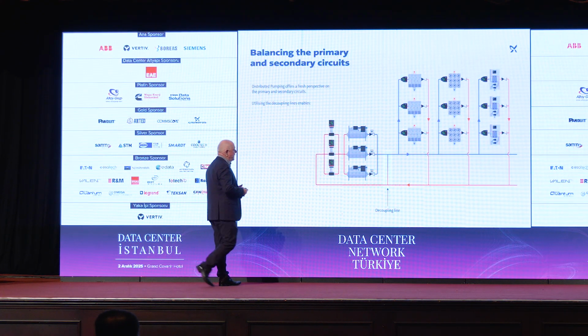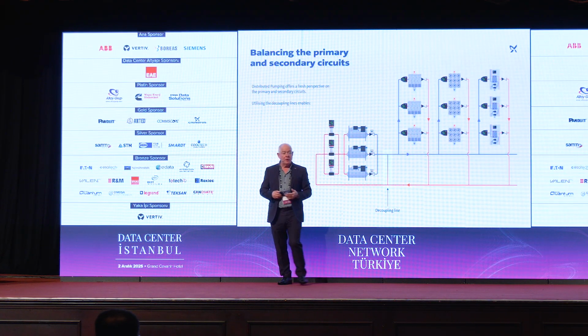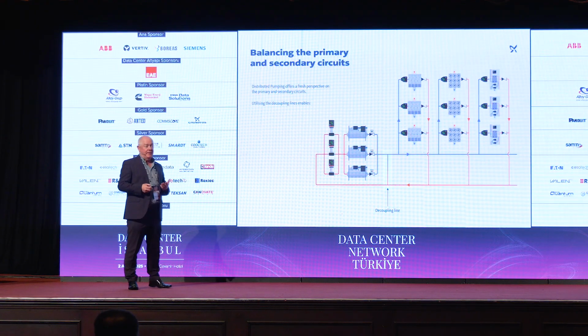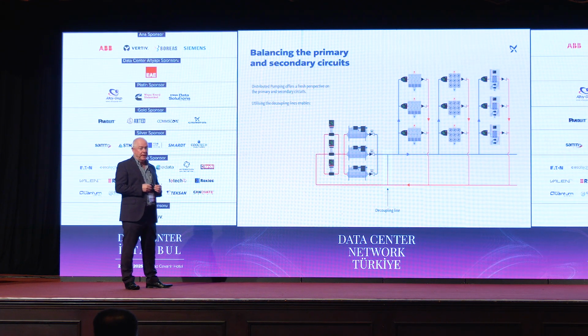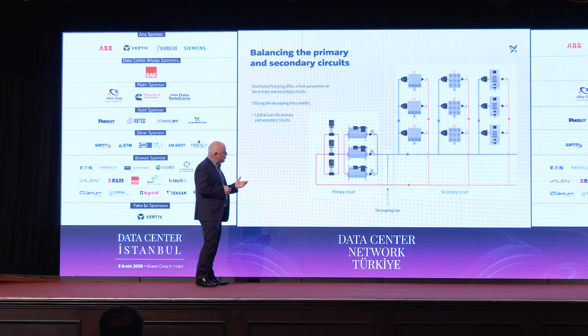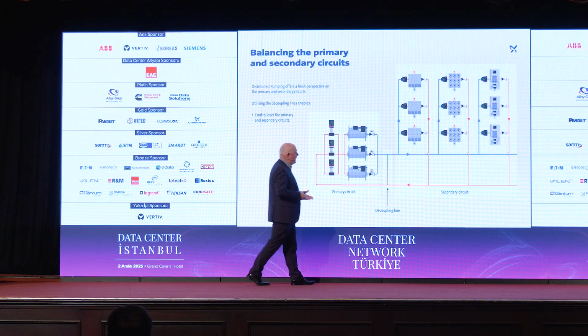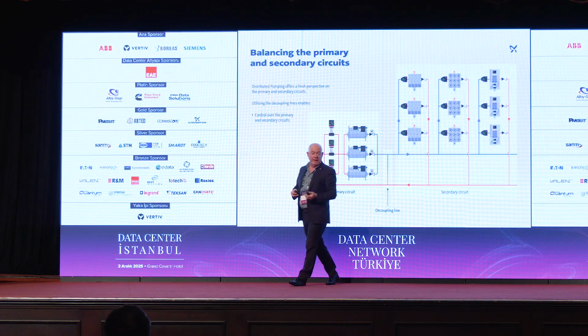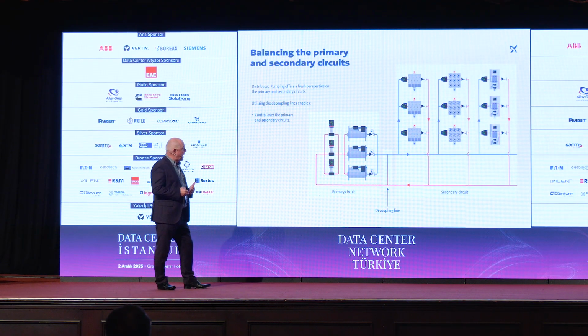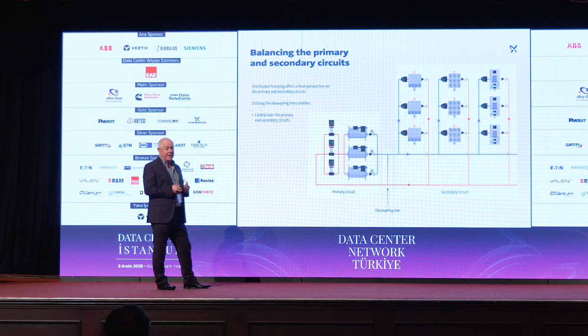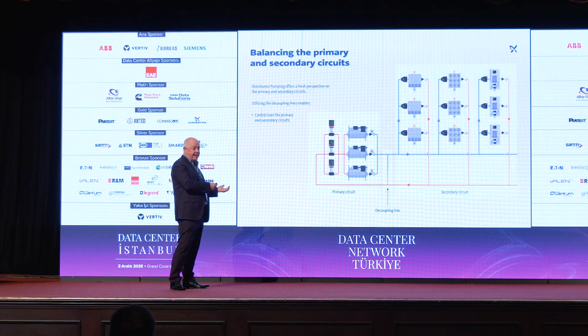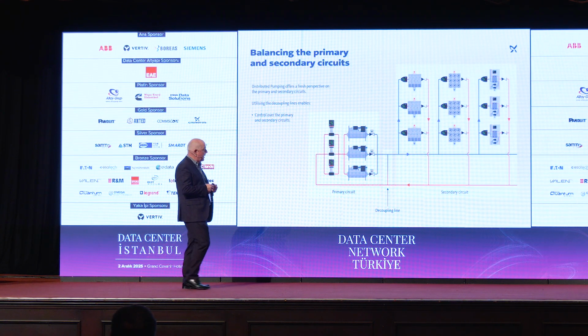So as I mentioned, we use this decoupling line, and in the ideal situation, we won't have any flow in the decoupling line when the system is fully balanced. If we need to pump more than the minimum load, then we'll circulate water through the decoupling line to save the system. And we control the primary pumps based on what's happening on the secondary side. The whole idea of the primary side is to provide just enough cooling water to meet the secondary loads. Each secondary load will have a pump on the system, and that pump will be connected to a sensor or BMS or whatever, and it will regulate flow to the cooling load in accordance with what that demand is. So we're all the time monitoring that and providing just enough cooling for the actual load, and then we're sensing this on the primary pumps and meeting the complete load. And I'll go through how we do that now in a second.